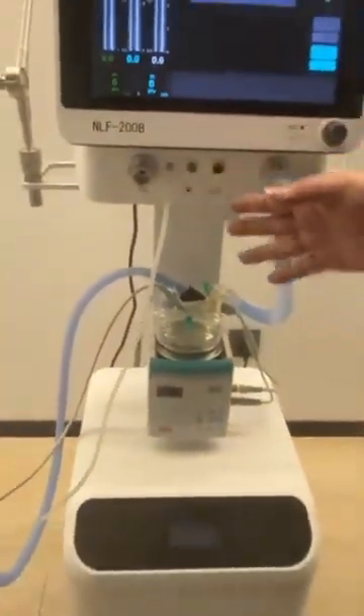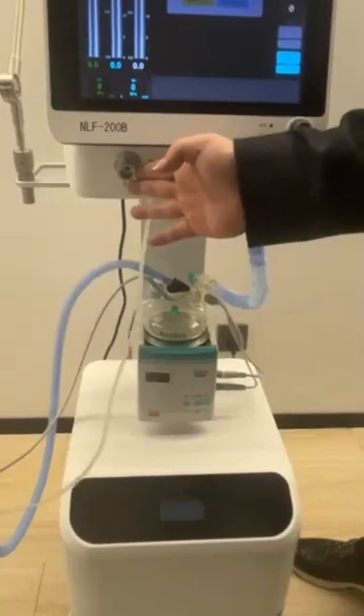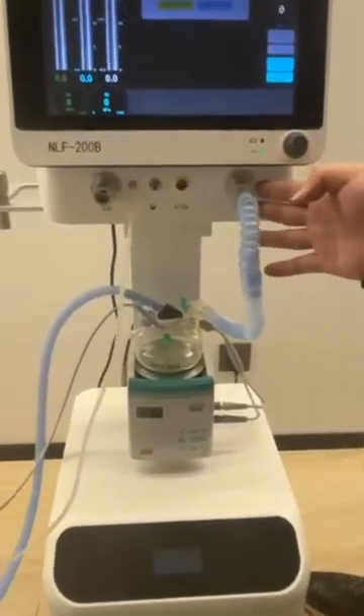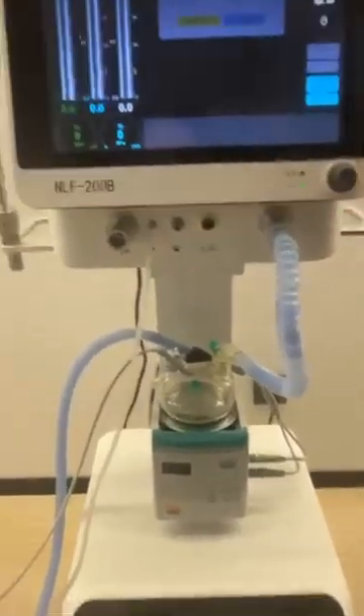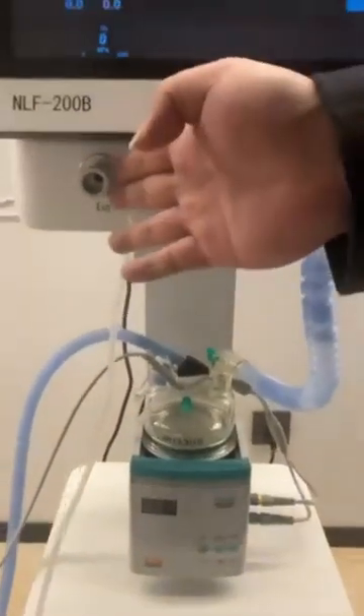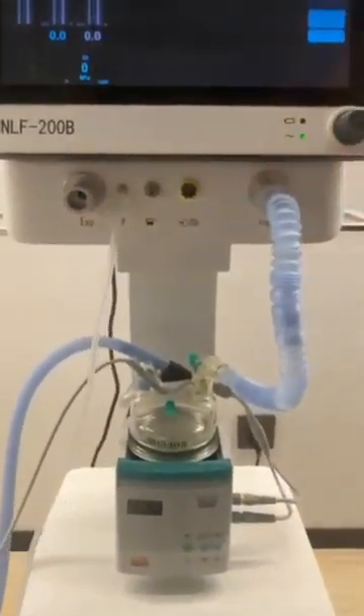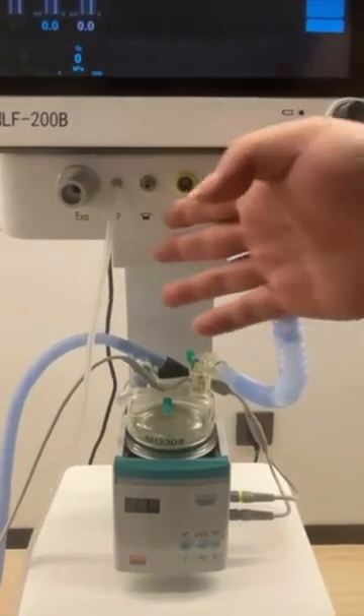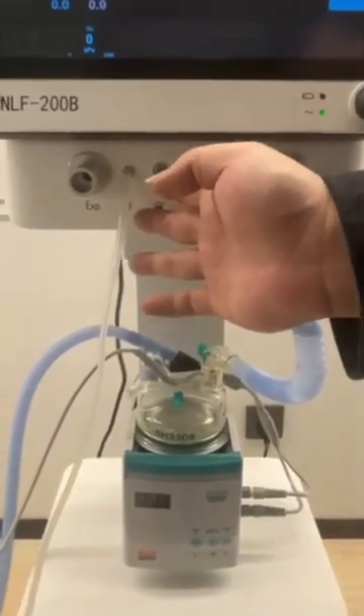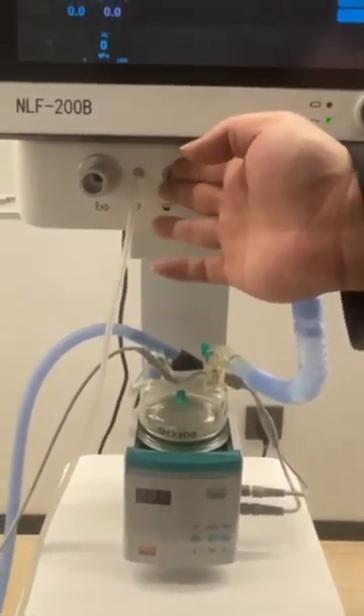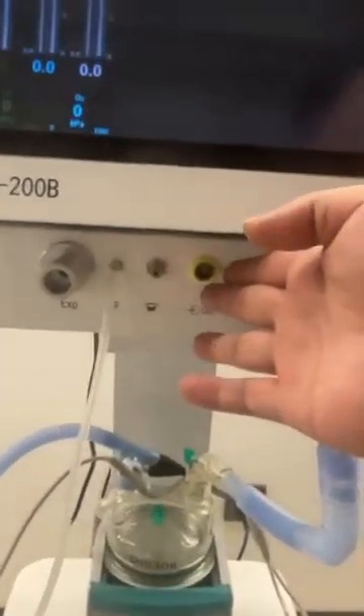So the next part will come to this part. We can see there are different ports. This port is the expiration port. This port is the inspiration port. If we are using a double tube connection, then both this port and this port will be connected, and also with the humidifier. And in the middle here, this one is connected with the nebulizer. And this one is the ETCO2.